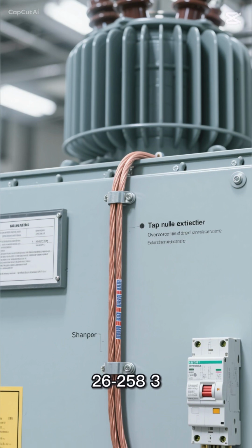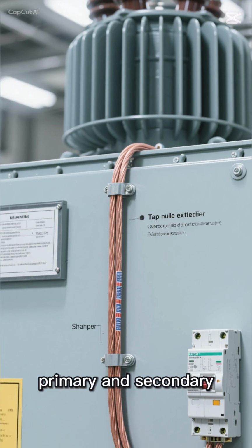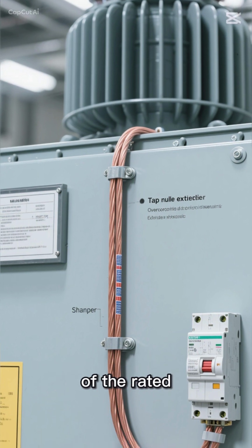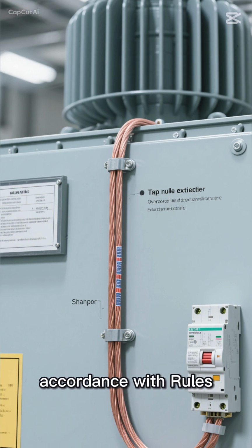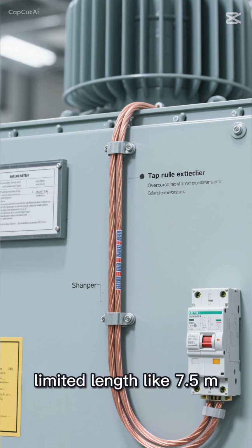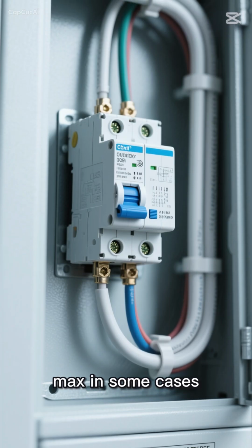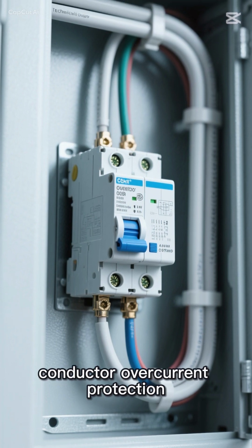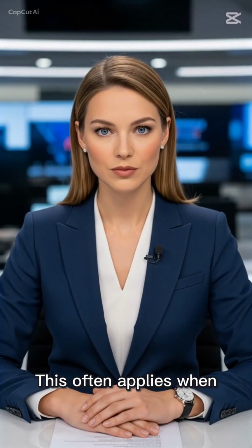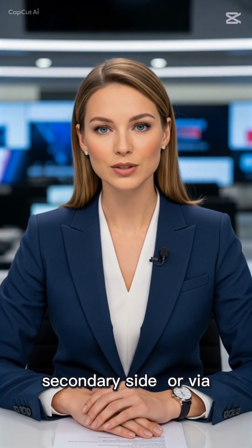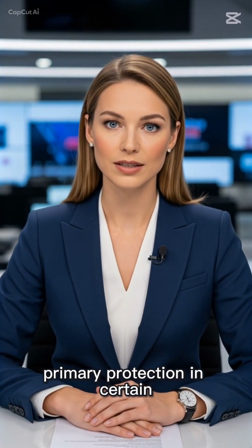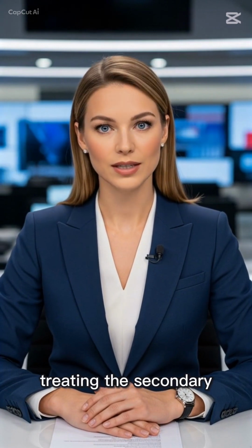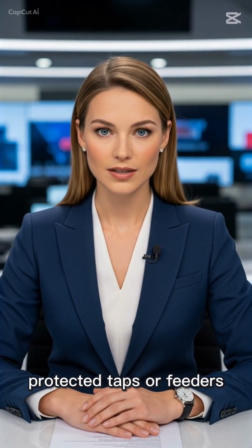Exceptions allowing smaller conductors. Per Rule 26-258-3, primary and secondary conductors are permitted to have an ampacity less than 125% of the rated current if they are protected in accordance with Rule 14-100. Tap conductor rules, e.g., limited length, like 7.5 m max in some cases, and 14-104, conductor overcurrent protection. This often applies when overcurrent protection is provided on the secondary side or via primary protection in certain configurations, effectively treating the secondary conductors as protected taps or feeders.